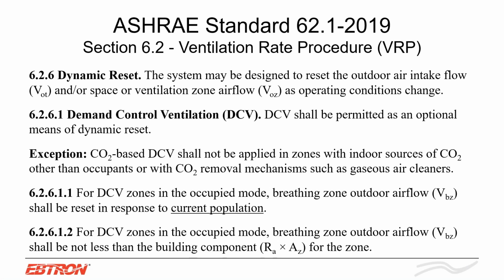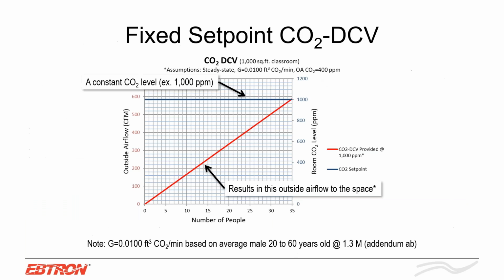ASHRAE says that DCV shall be permitted as an optional means of dynamic reset, and that for DCV zones in the occupied mode, the breathing zone outdoor airflow, Vbz, shall be reset in response to the current population. So again, as the population is changing, the required amount of outside air to the space is going to change. This is a typical fixed set point CO2 DCV strategy, and we're assuming steady state, we're assuming no lag, we're assuming no error associated with your DCV sensor. We're assuming an outdoor CO2 level of 400 parts per million, and we're assuming a CO2 production rate based on average males 20 to 60 years old. So again, this is what a lot of designs typically do.